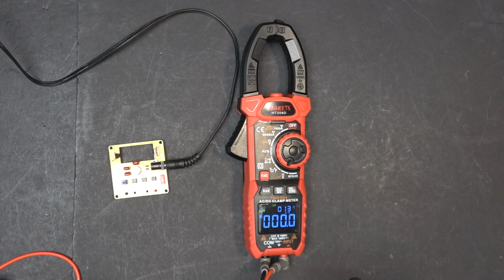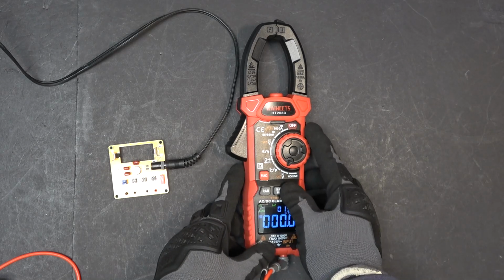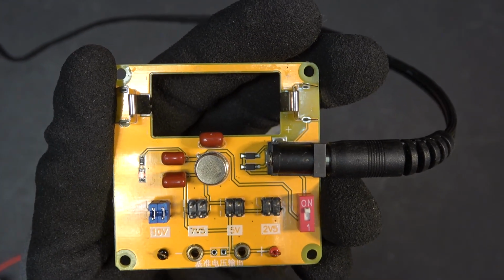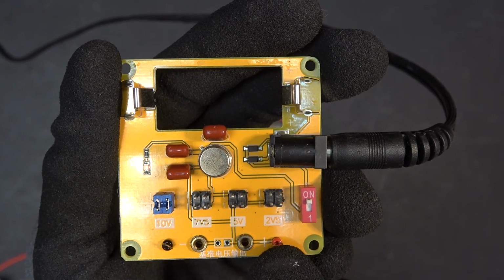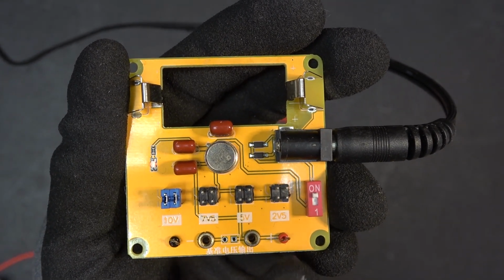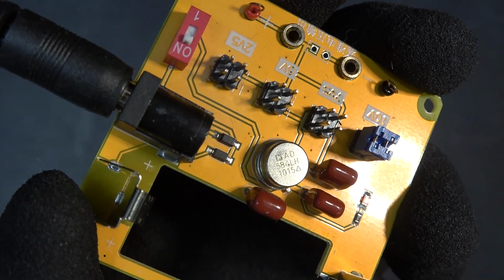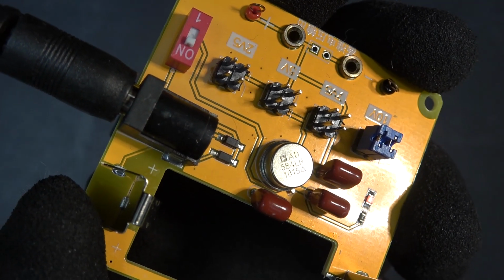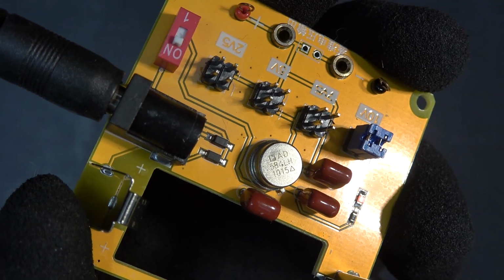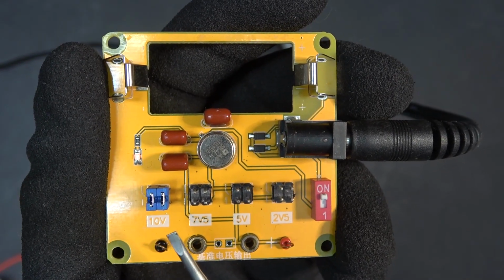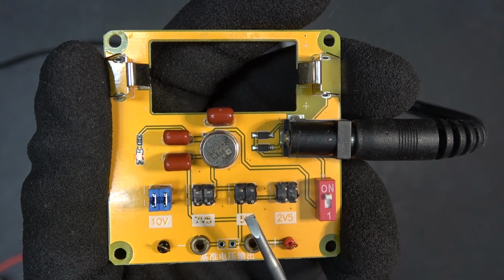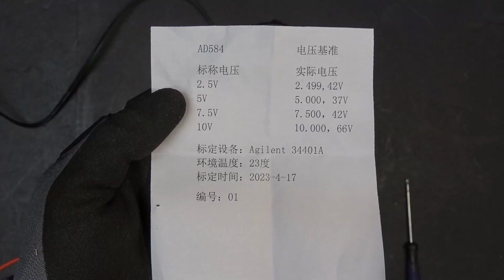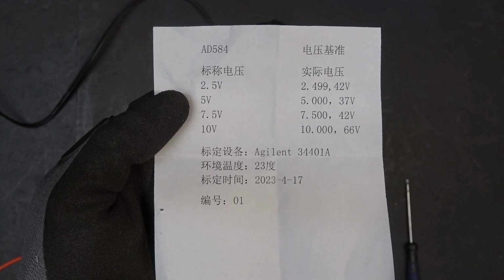Talking about voltages, I want to test the voltage reading on this meter, see how accurate it is. So let's turn this dial to volt reading. I have a voltage reference board here. It's used to calibrate and test voltages of multimeters. It has an AD584 chip, which will put out very accurate voltages. In this case, it will put out 10 volts, 7.5 volts, 5 volts, and 2.5 volts. And this is the test result for the chip.